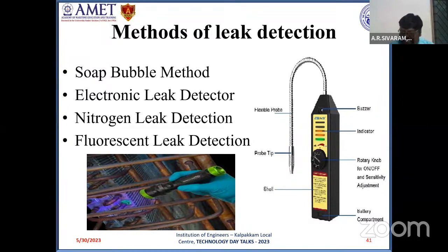Suppose a system has 10 leaks, 20 leaks, or more, then obviously we go with nitrogen leak detection. That is, nitrogen is charged inside the system and left for one day. If there is no pressure drop, all leaks have been completely arrested. If there is a pressure drop, it means a leak is still present in the system and needs to be arrested. This is used as an overhauling method, a nitrogen leak detection testing method, when the system has a large number of leaks.